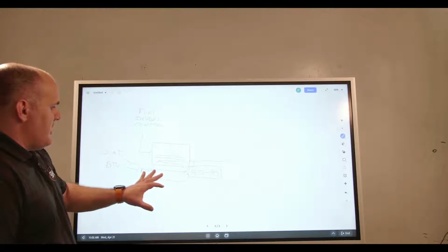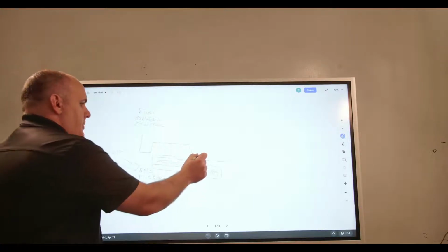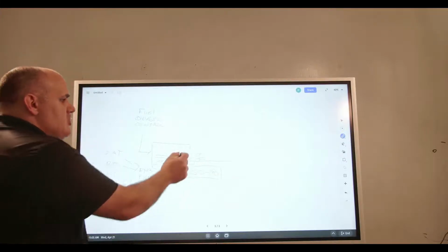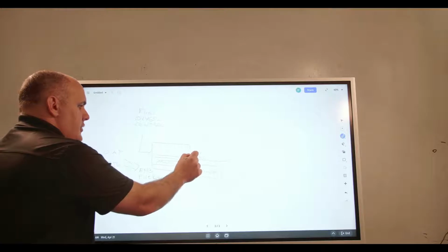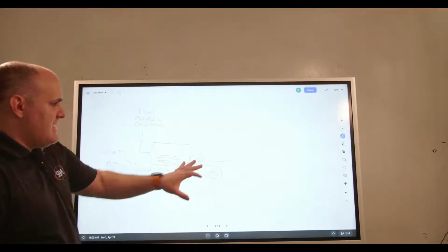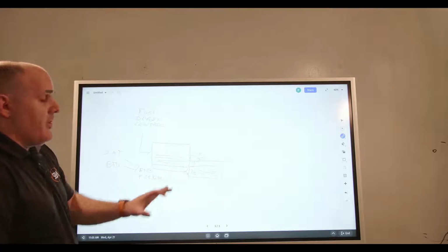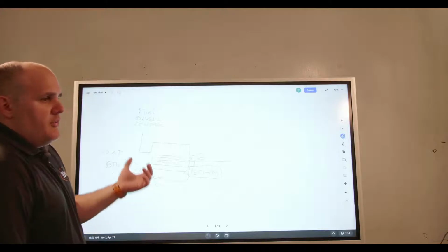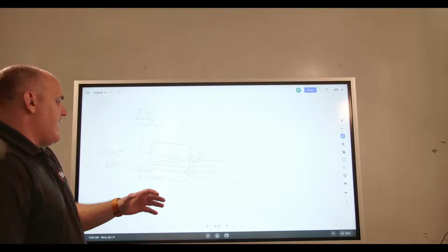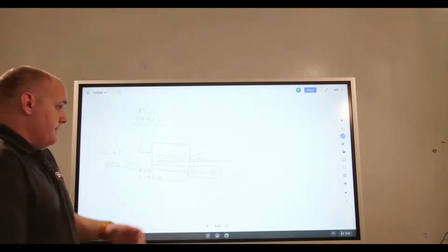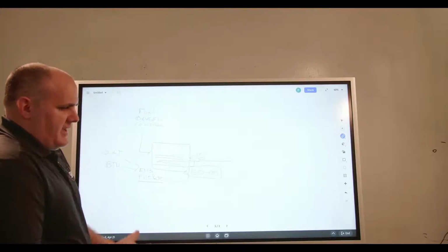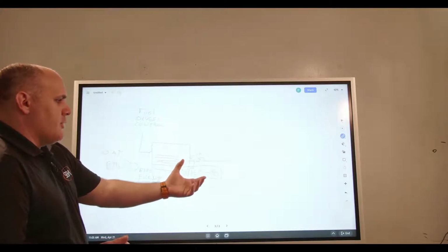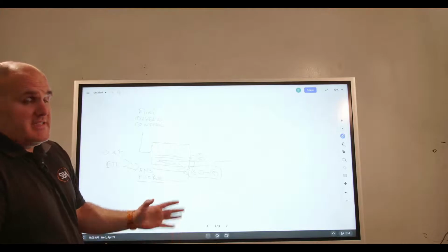But what happens, right, we enable the boiler, we enable the pump sometimes. There's a circulation pump, a CP, that's usually interlocked to the actual panel right here. Now that CP is enabled typically when the boiler is enabled, and when it proves flow, then we'll move into ignition, we'll move into low fire, and then we'll move into high fire unless we have variable fire rate, okay? So low fire being a low amount of fuel being burned, high fire being a high amount, and the boiler itself will control to its primary temperature, all right?